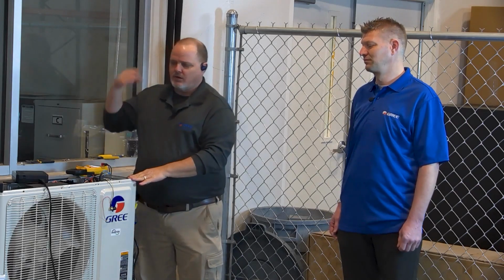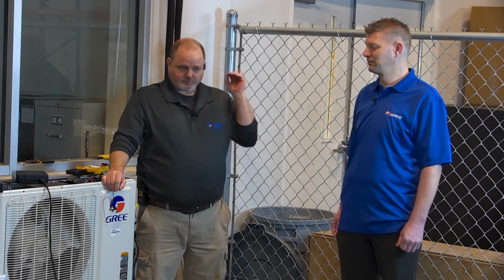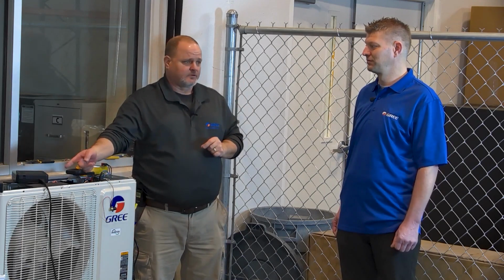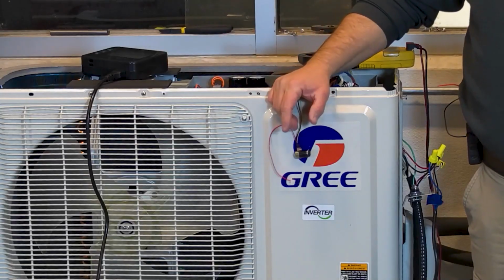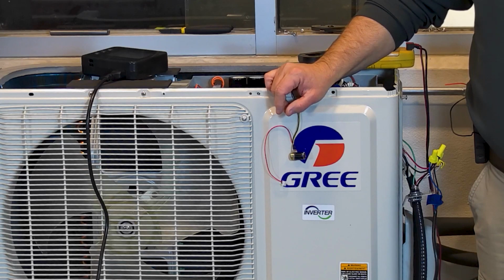Yes. So one of the biggest phone calls we get into tech support is about E6 troubleshooting, which is a communication fault between the indoor unit and the outdoor unit. They can't talk. And when it can't talk, it don't run. That's the biggest one. The error code troubleshooting we have does a really good job with all the voltage readings and stuff, but I'm here to tell you it does not replace this tool. This tool is so much easier to do an E6 troubleshooting.